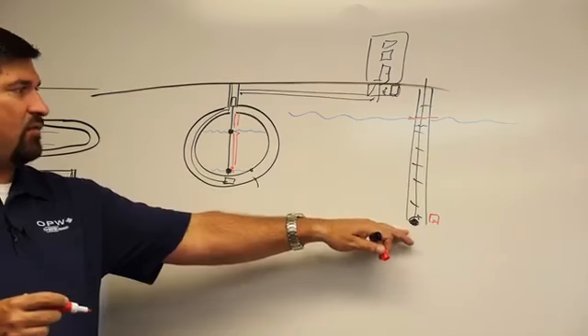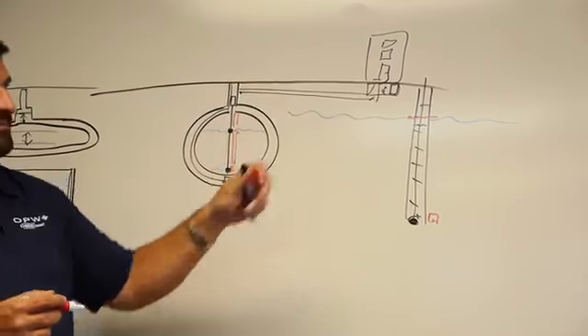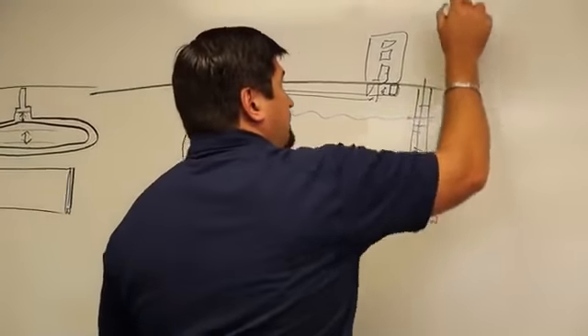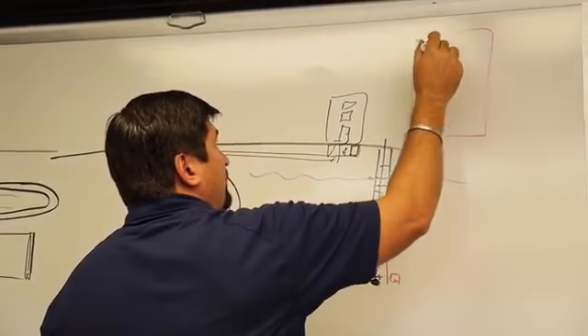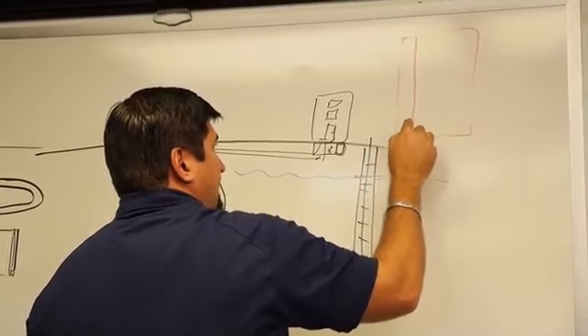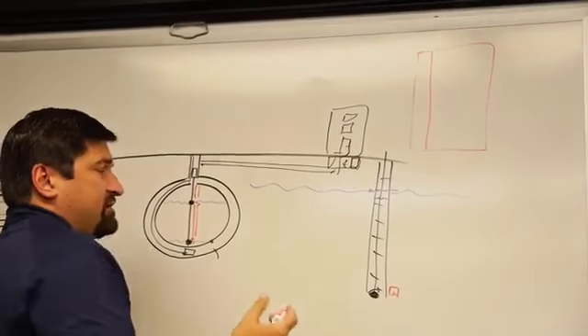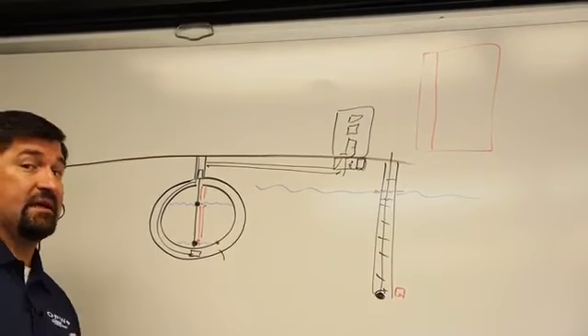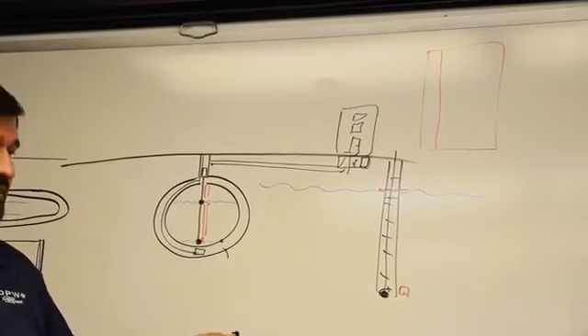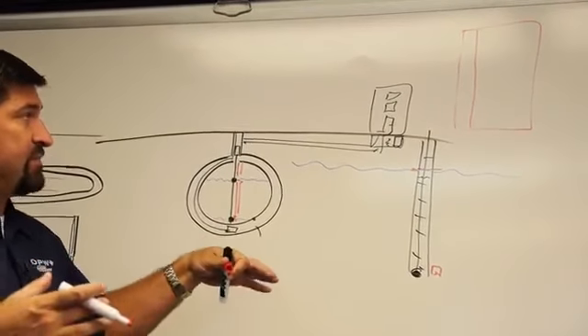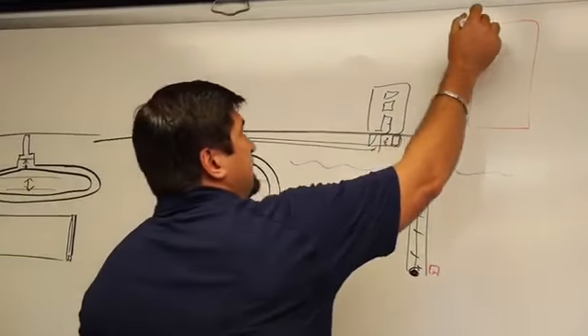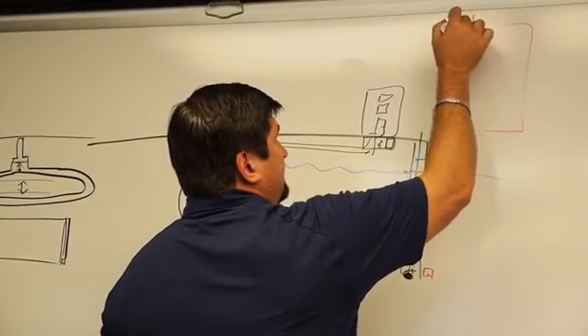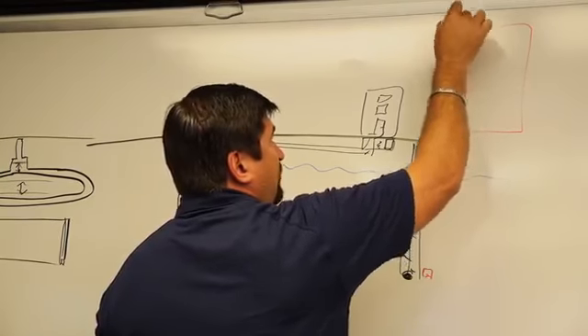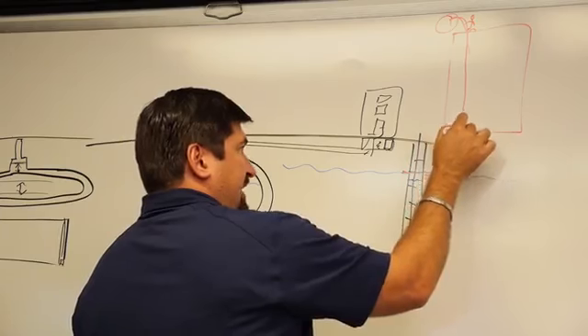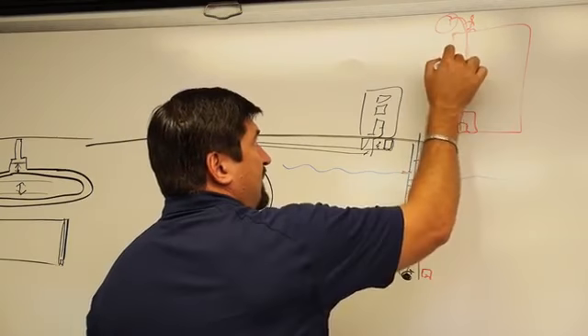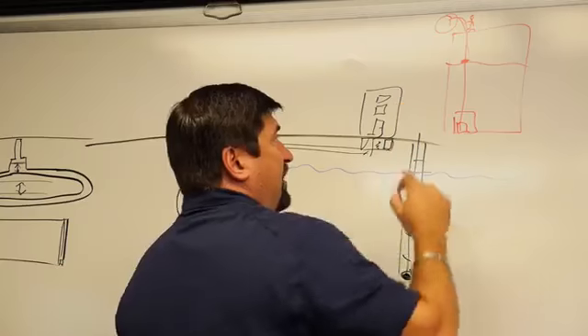So this is a groundwater well, a dispenser sump, but we also have the very tall tanks, anything over 20 foot. We also have what's known as a flexible probe. Now a flexible probe can go up to 70 feet, and it comes in a coil in a 4-foot round circumference, but it'll come in a box. And you're just taking two people, putting on top of the tank and uncoiling this probe into the tank. Same thing, it'll have a weight, it'll have a water float, and then you have a product float.